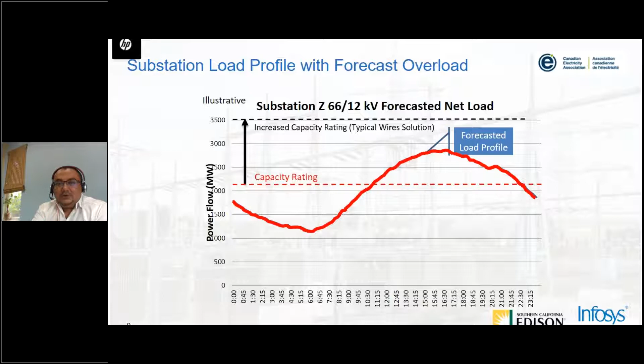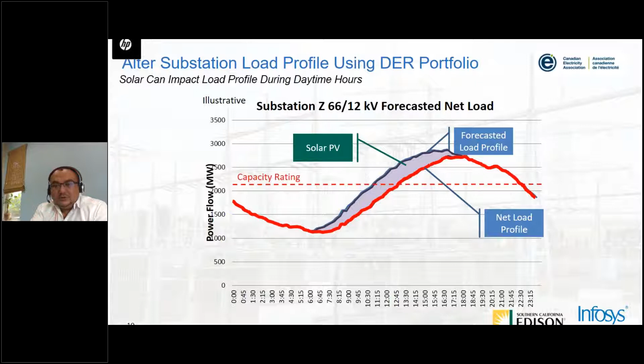So this is just the forecasted load profile showing it's going beyond the capacity rating of the substation. And this is probably a cumulative effect of the DERs for that substation - we see that the peak overall consumption is coming down just through the use of solar PVs across the network. This is called the net load profile, and this is already happening today because of the DERs available across the territory. So we can already see shaving of the load to an extent.